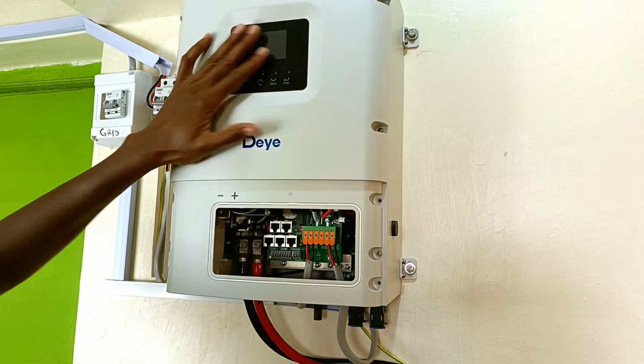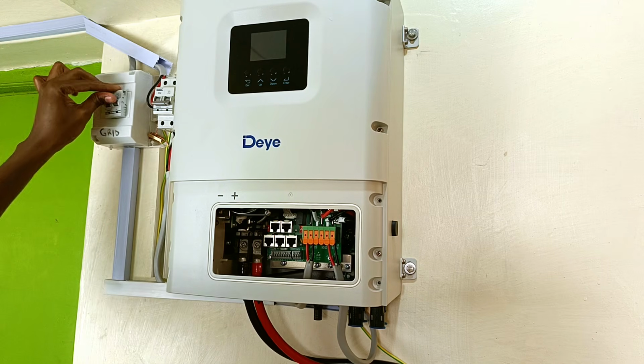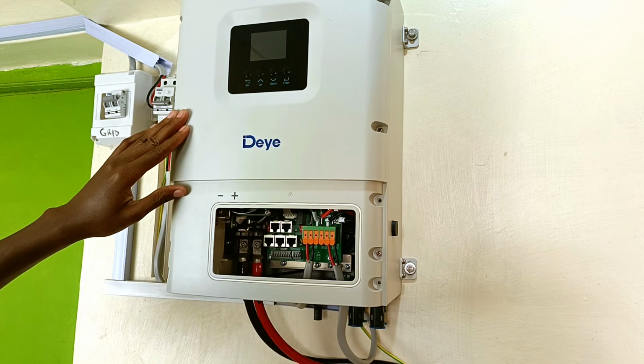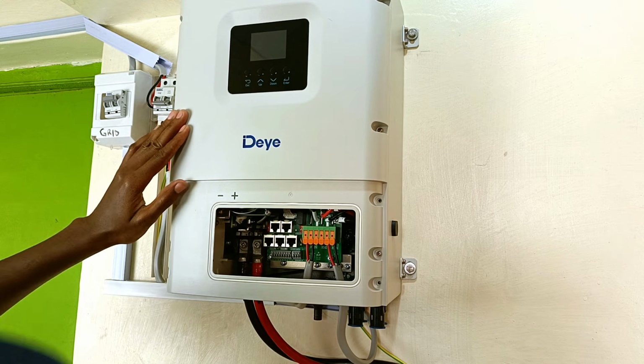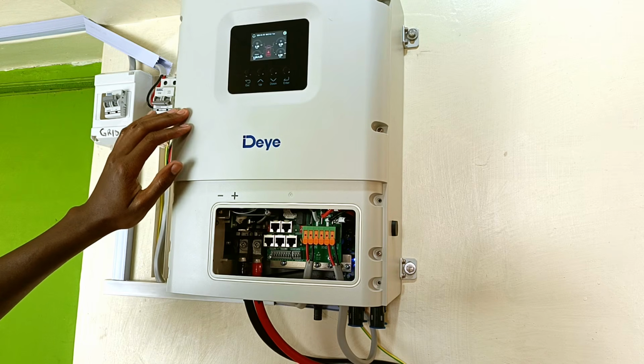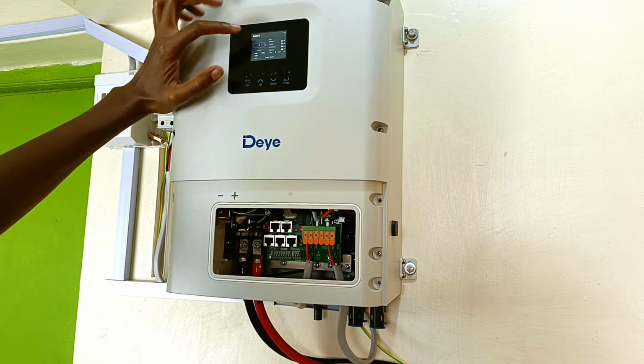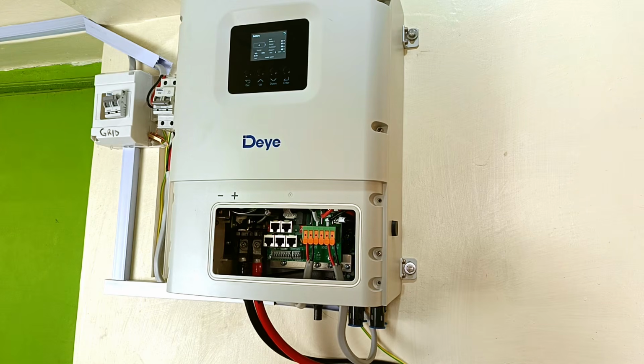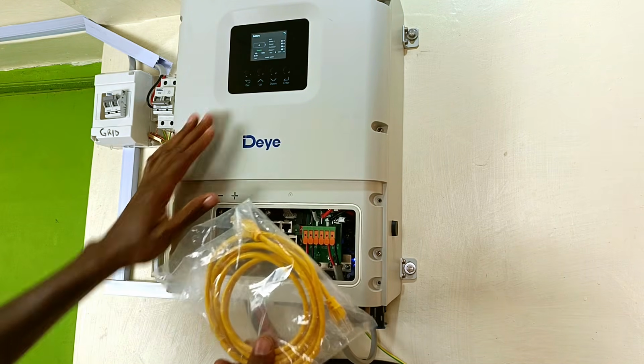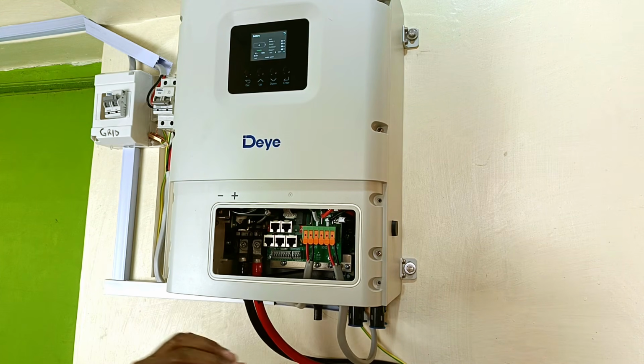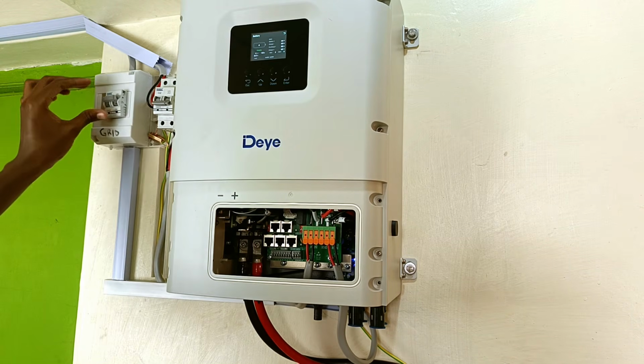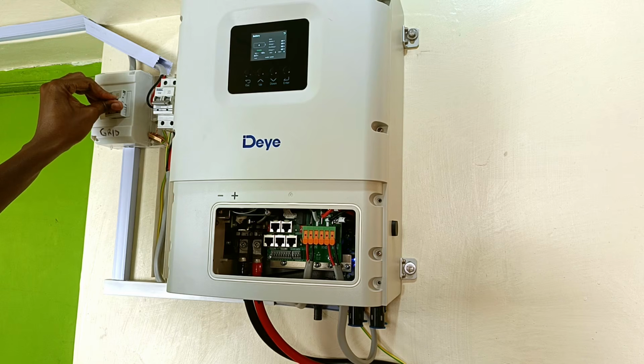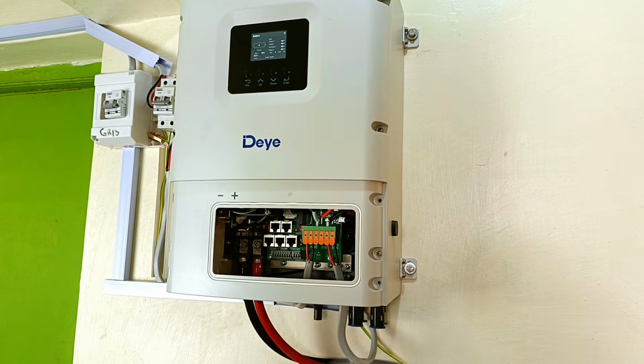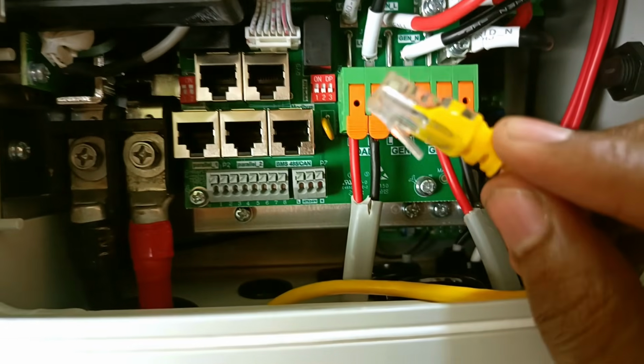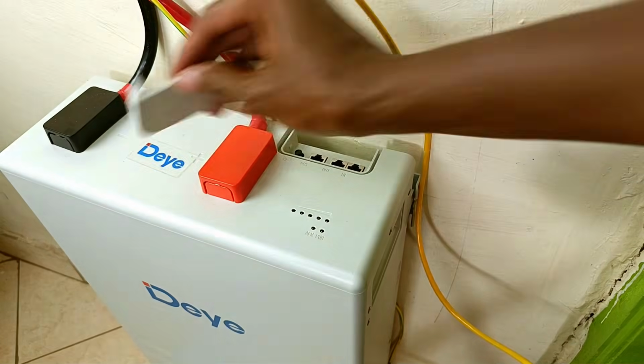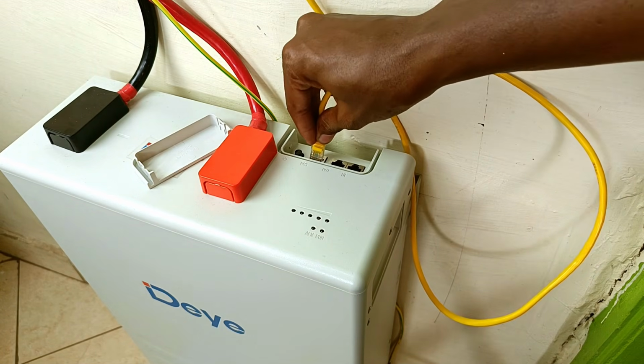If I turn this breaker on, this inverter should turn on. And indeed, it is on, but the battery is saying 0. So I first of all need to connect the communication cable from the inverter to the battery and have that communication done. But in order to do that, I first of all need to turn off the AC from the grid. On the inverter side, it's supposed to go into the BMS port, and on the battery side into the PCS port.